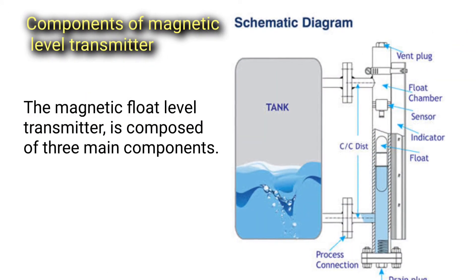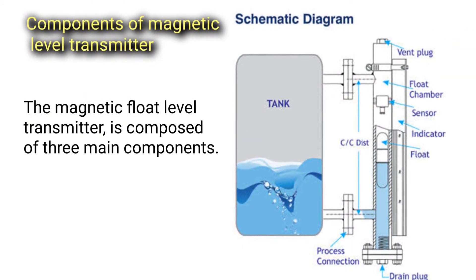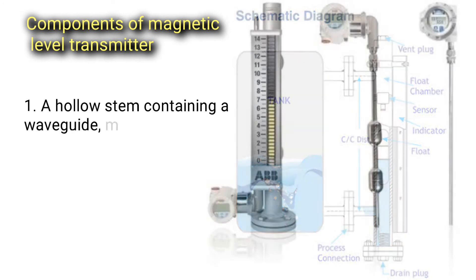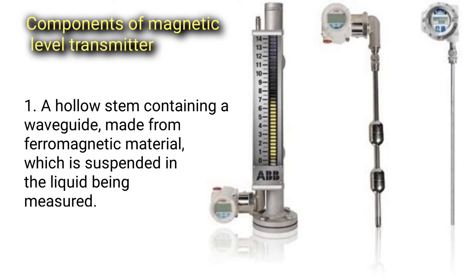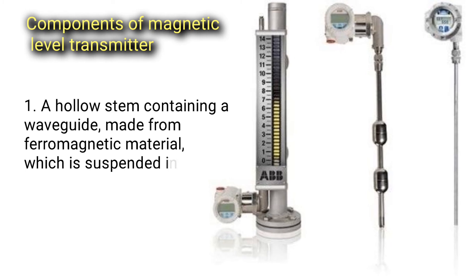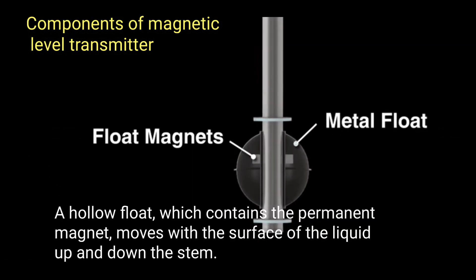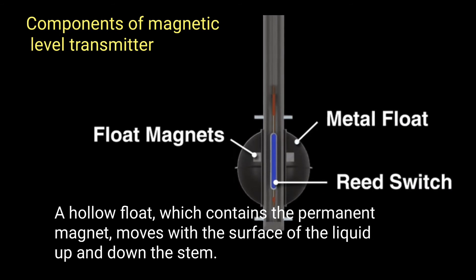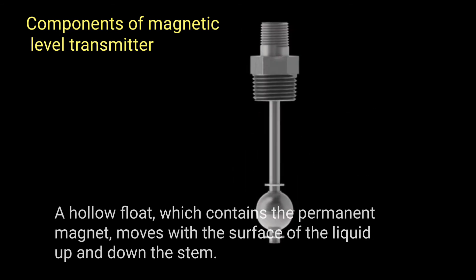The magnetic float level transmitter is composed of three main components. One, a hollow stem containing a waveguide made from ferromagnetic material which is suspended in the liquid being measured. Two, a hollow float which contains the permanent magnet and moves with the surface of the liquid up and down the stem.